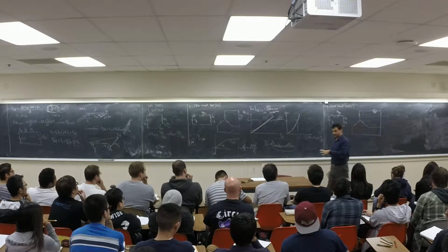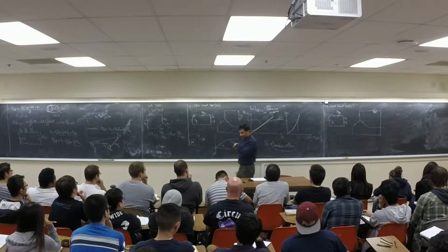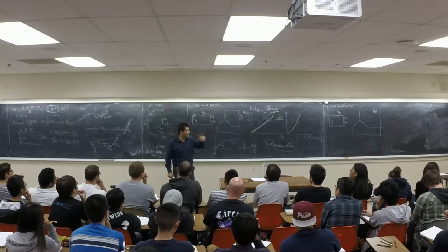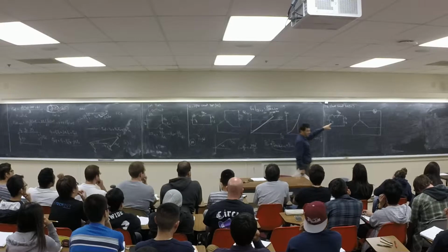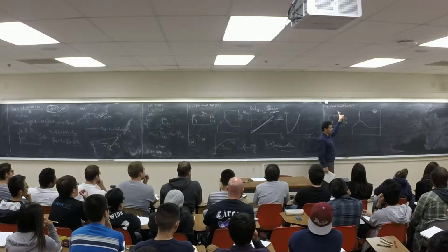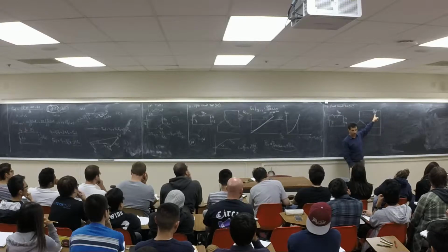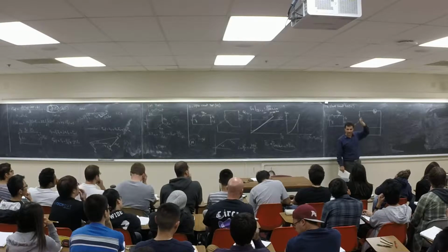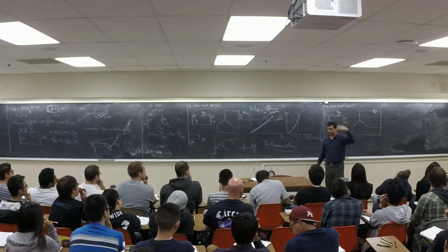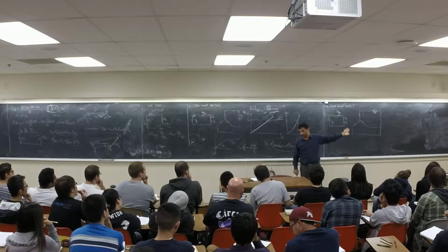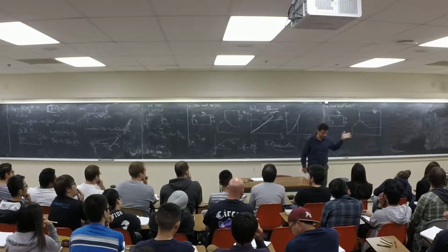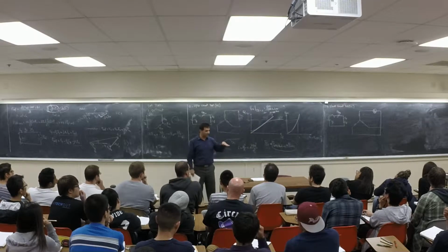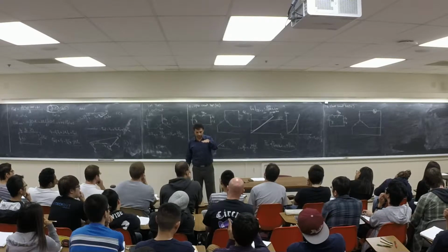Exactly like a transformer. When we did the short circuit test, we said we short the secondary of the transformer very, very carefully. We bring up the voltage and we look at that current, ISC, right? We start to increase this one slowly and we monitor this current to make sure this current is not more than rated current, right? The current is going to go up, up, up. We keep it maybe 5% or 10% more than rated current, not more than that. And we stop the test very quickly. We are not going to keep it at 10% for like 10 minutes because that is going to make the machine very hot, right? But you do this because you want to have a little bit more information. You can go a little bit over the rated current, right?